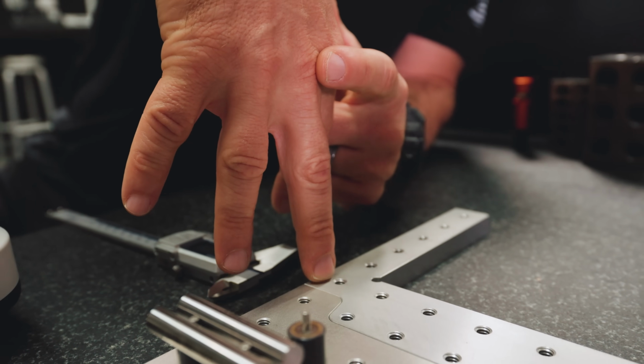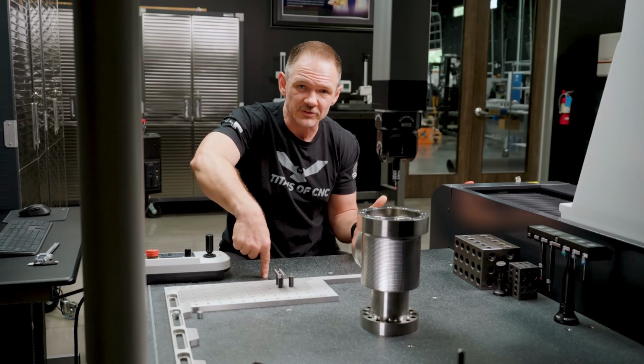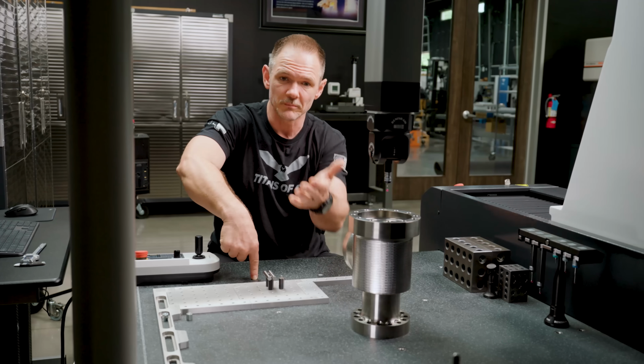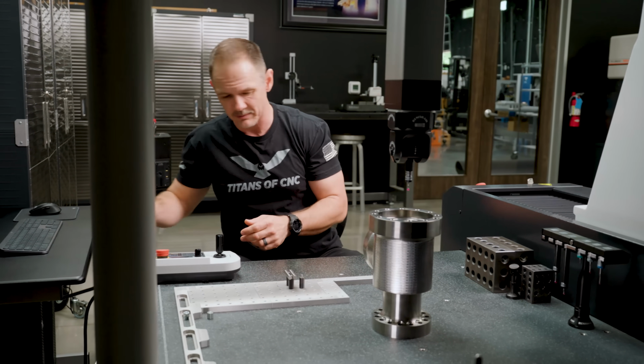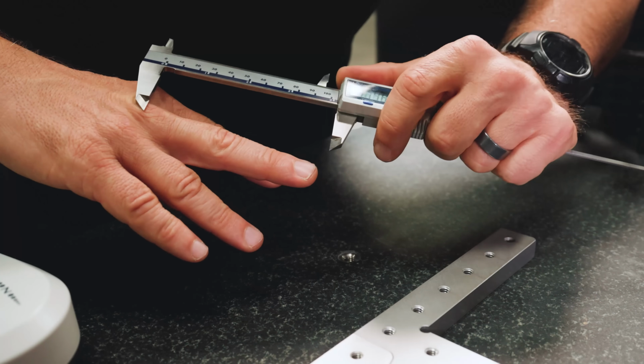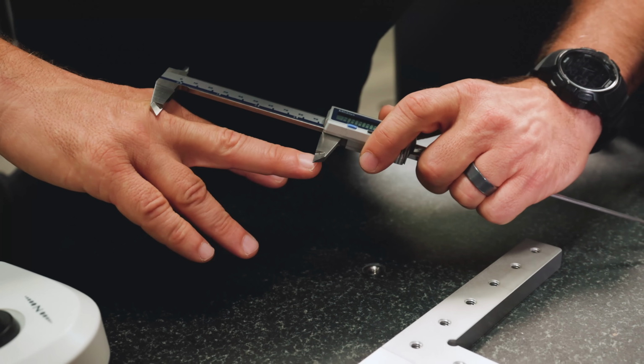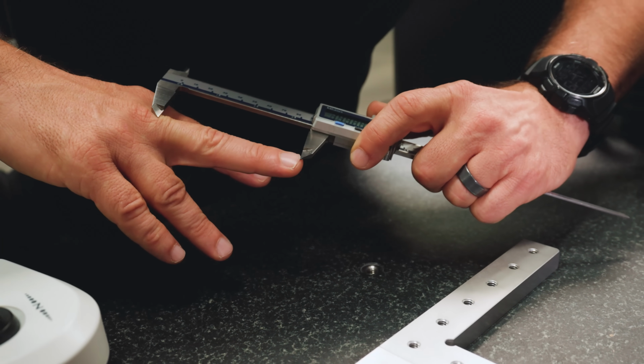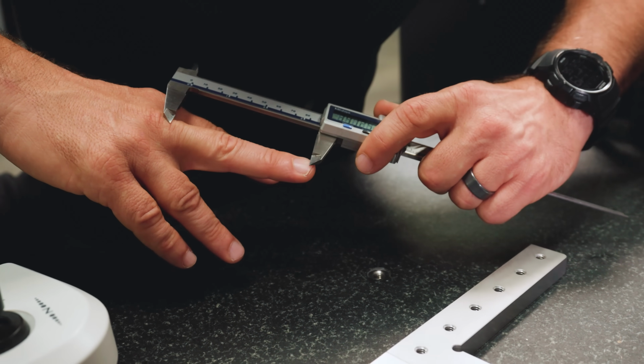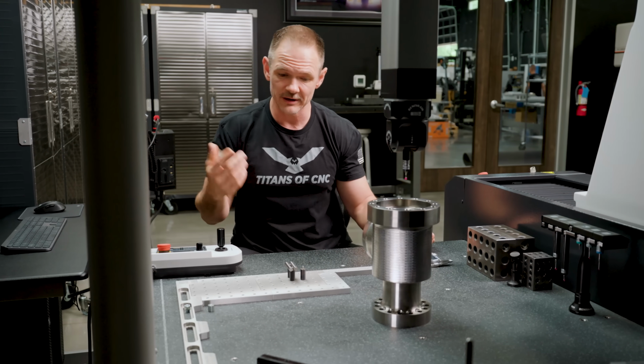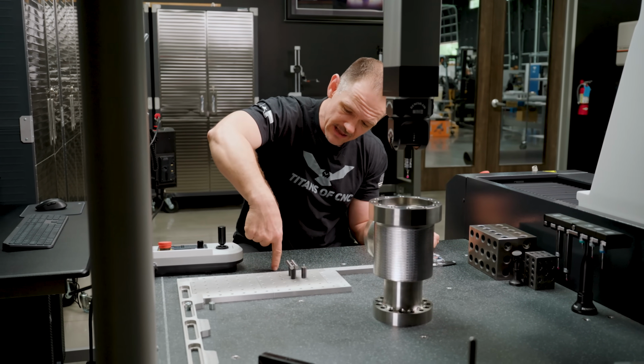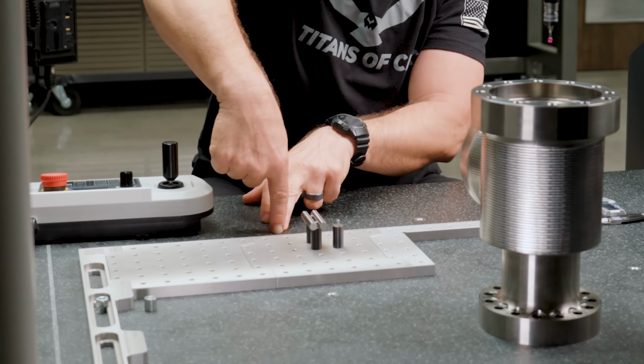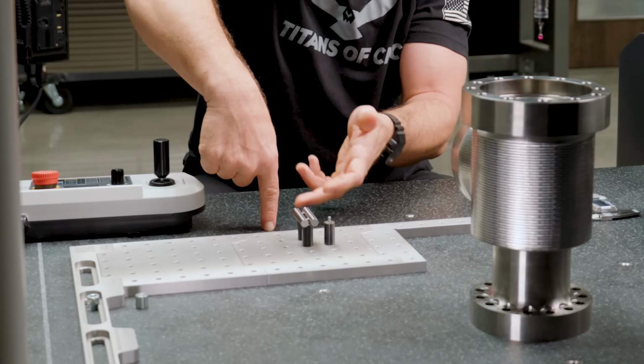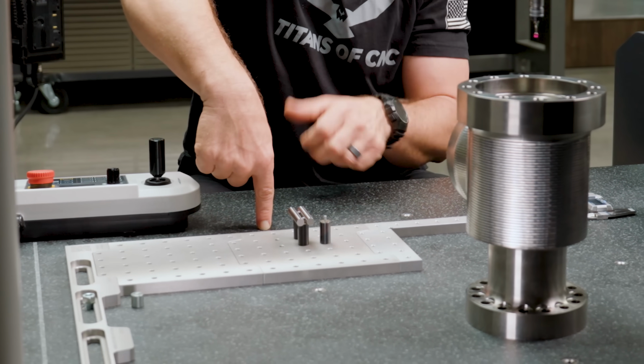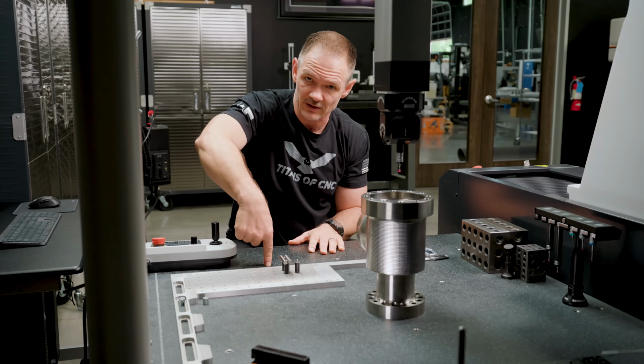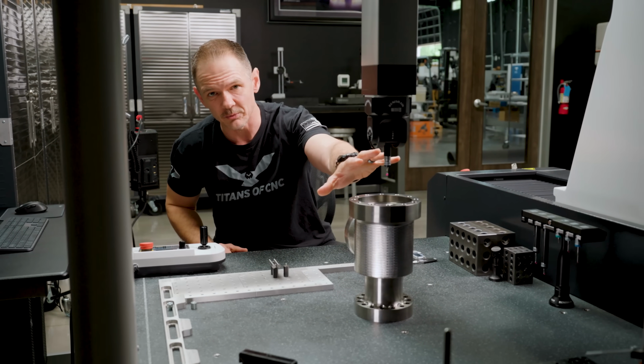Now, I don't know exactly if it's 3 inches—what if my finger is a little less? Let's calibrate my finger, much like I would with the ball. If I take a pair of calipers, pretty rough and ready, we calibrate and find that from my knuckle to the tip of my finger is actually 3.143. Now I've calibrated my finger. When I come down and touch, and feel that pressure or bend a little—kick off the seat—I know the position of this table is 3.143 below my knuckle. That's essentially what's happening with the CMM.